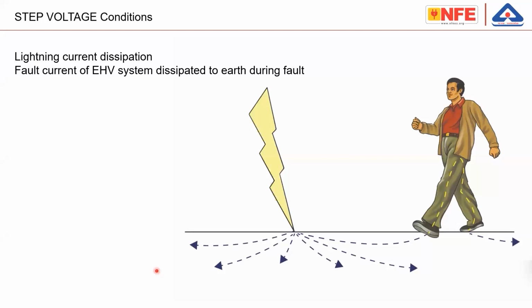Now the standard has recommended how to get rid of this step voltage. For example, if you are near a tree, you have to be at least 10 meters away—meaning up to 10 meters from the tree, step voltages can injure a person. In a very good lightning protected structure, probably it is 3 meters; from the structure outside, 3 meters is a danger zone. I have pictures, I will show you.